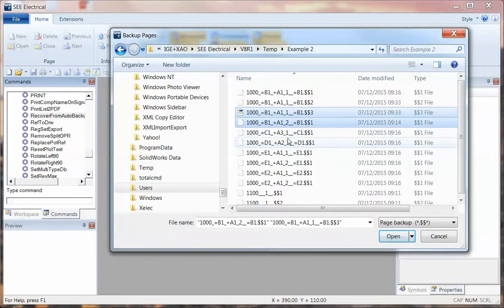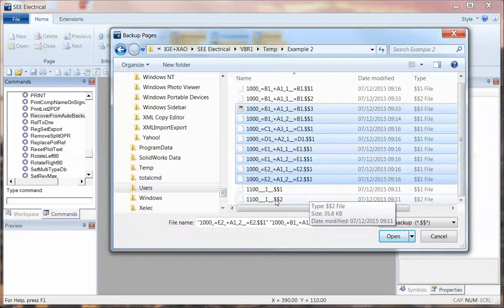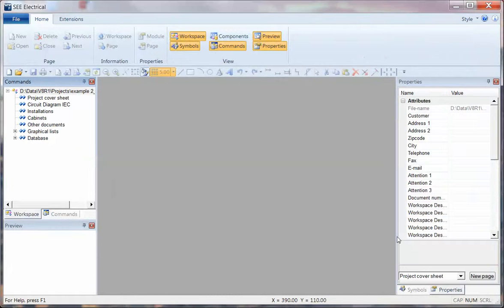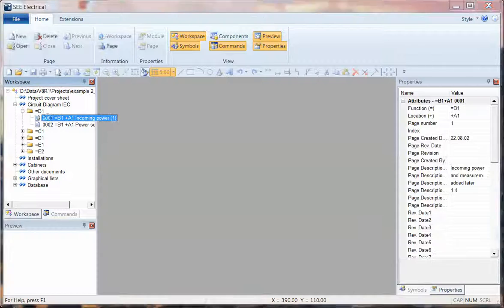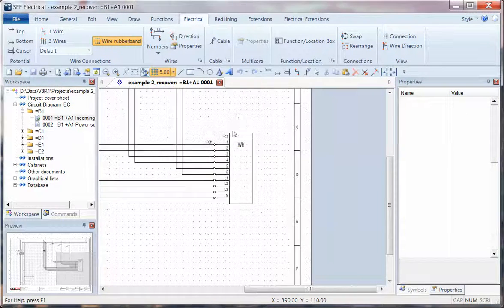Number three is the most recent version of that particular page — page number one for circuit diagrams. I'm going to select the most recent page from each of these. I'll hold down Control and also take the cabinet layout, taking the most recent version — number two. So I'm taking the third version of the first page, and all the others only have a single backup page. Now I'm reconstructing the project from those most recent versions. I click Open and the project is reconstructed — we can see it's there with the page descriptions and all the components exactly where we want them.